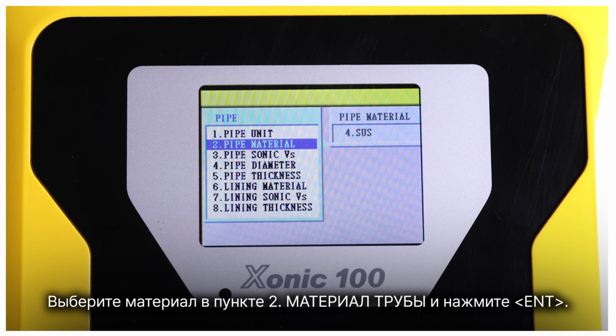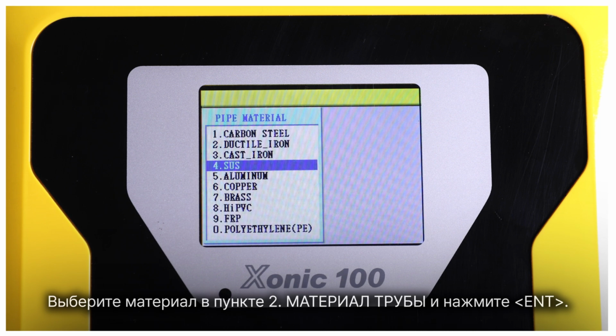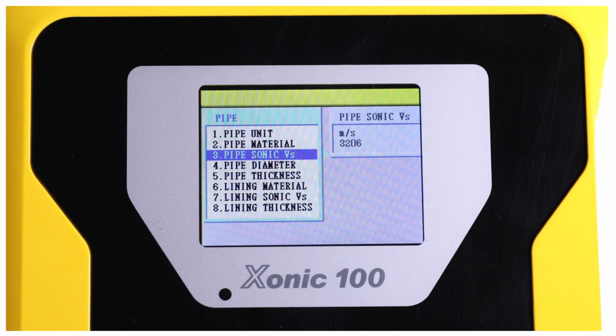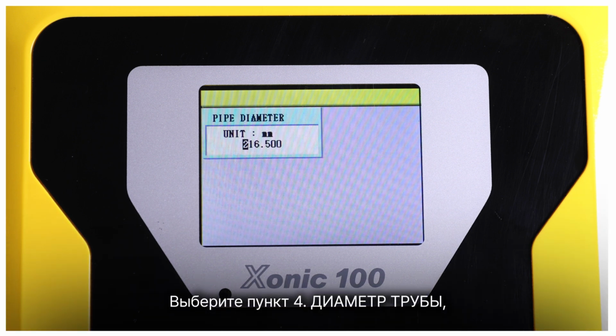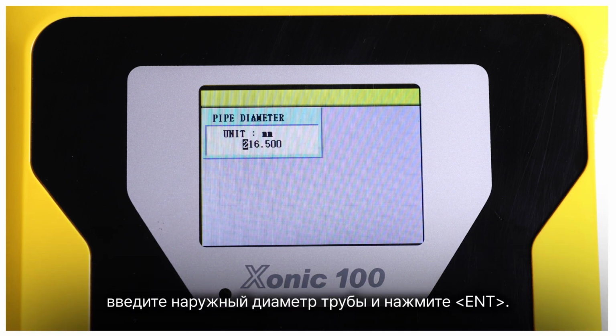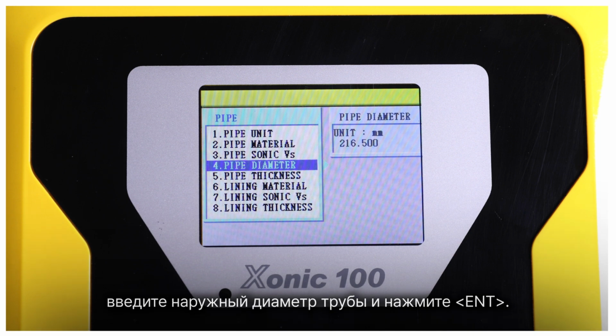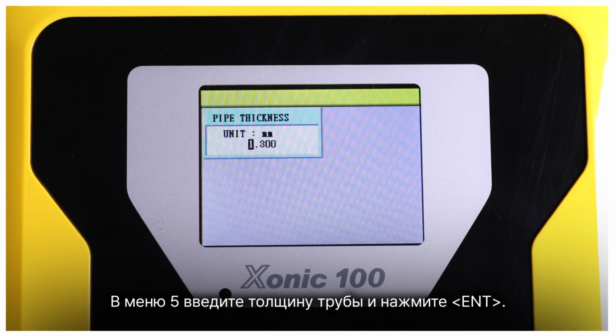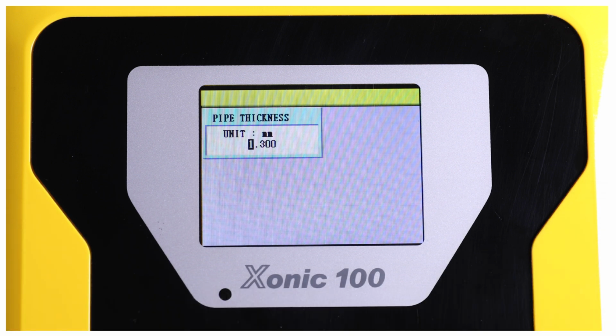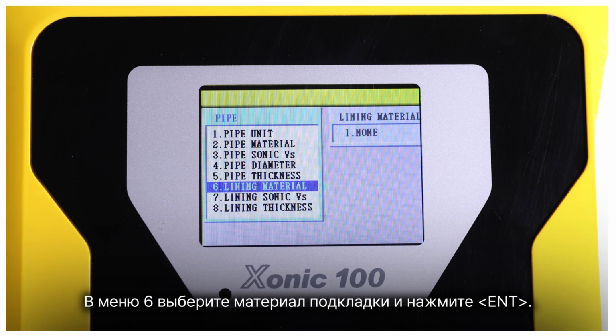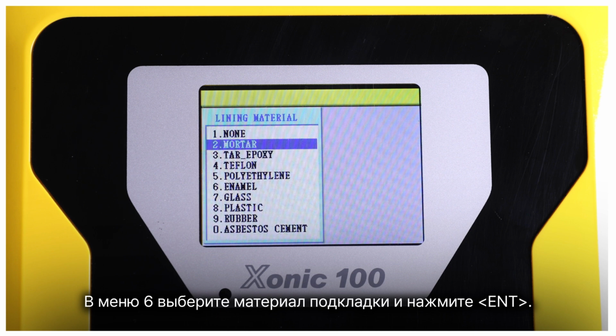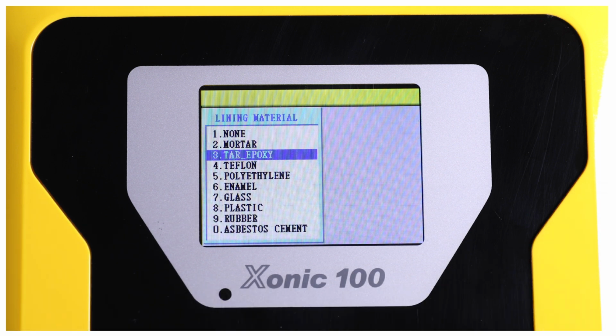Select the material on the pipe material menu and press enter. On 4, pipe diameter, input the outer diameter of the pipe and press enter. On menu 5, enter the pipe thickness and press enter. On menu 6, select the lining material and press enter. If there is no lining, select 1, None.